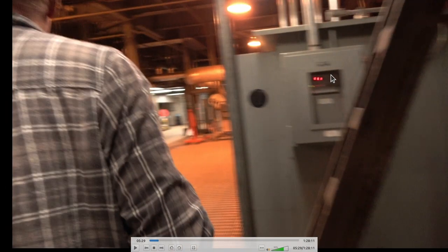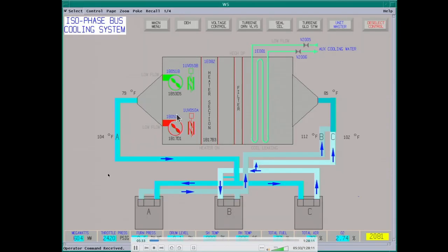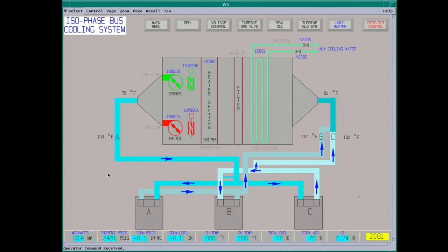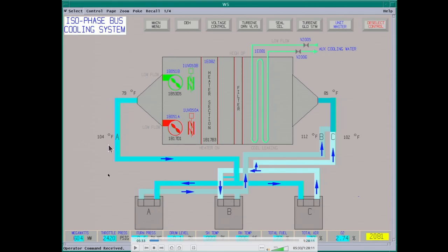That's your frequency monitor. This is the isophase bus cooling system — the power coming out of the generator goes through a duct with an aluminum conductor inside that is support-insulated. You blow air through to maintain temperature, and also heat it in the winter so you don't get any moisture buildup. Each transformer is tied into this, and each of the bus lines go through your isophase bus.